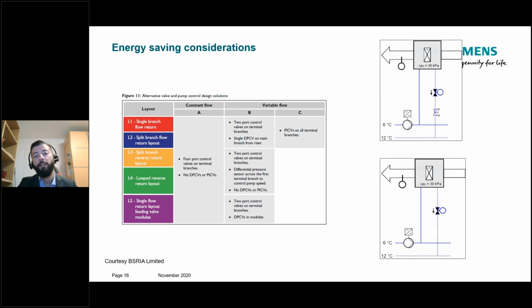And if you look at just the red and the blue piping layout up here, we can now compare the energy performance of the 2 different valve sets shown here. The first one at the top is a static control valve with a manual balancing valve. And there is, you don't see it, but there is also a differential pressure controller considered for the risers. And the second one is basically a PICV arrangement, so without manual balancing valves and without any other regulating valves along the main lines.